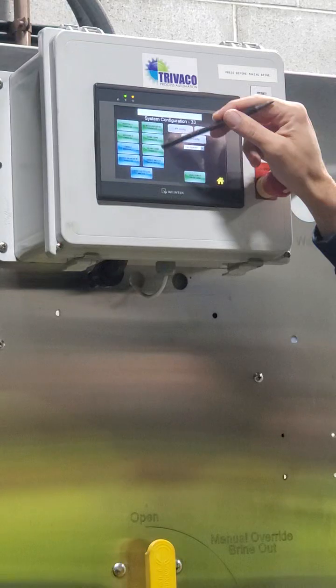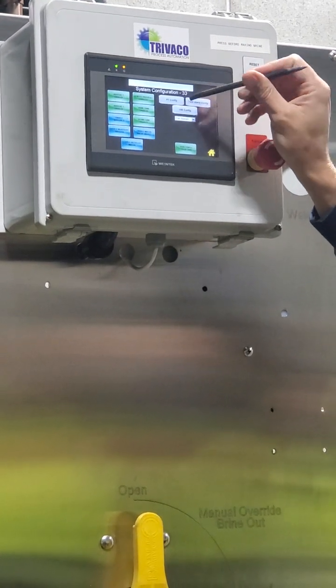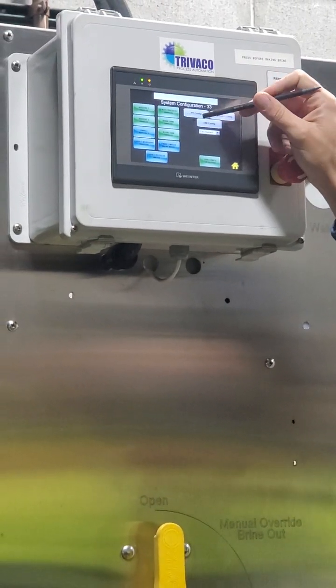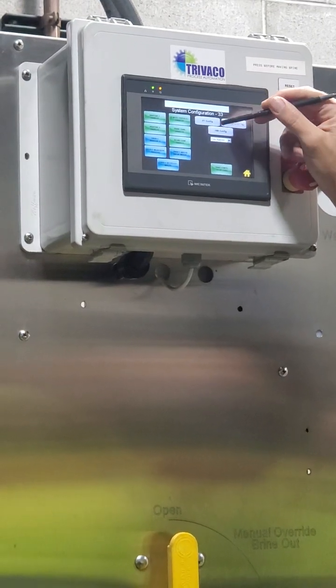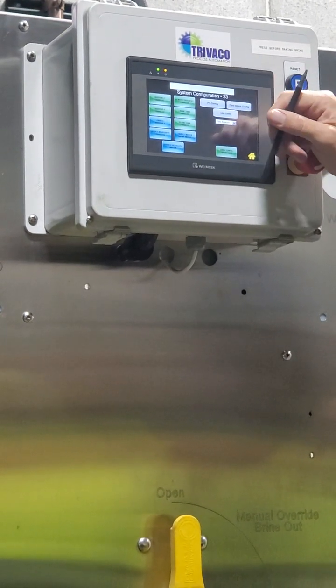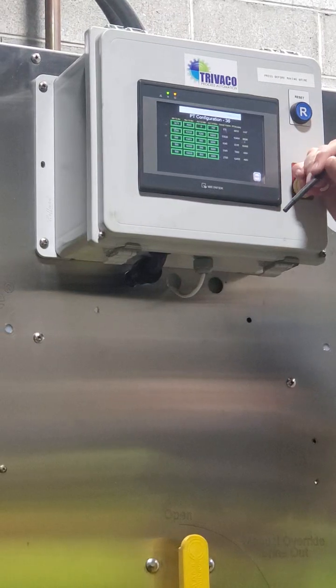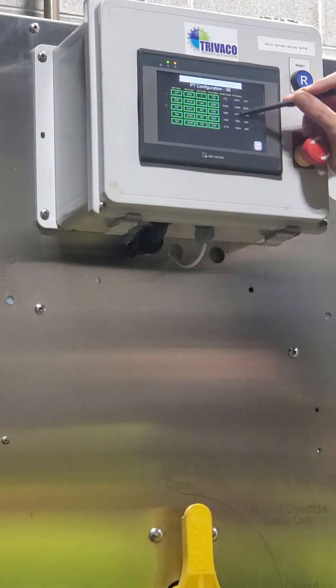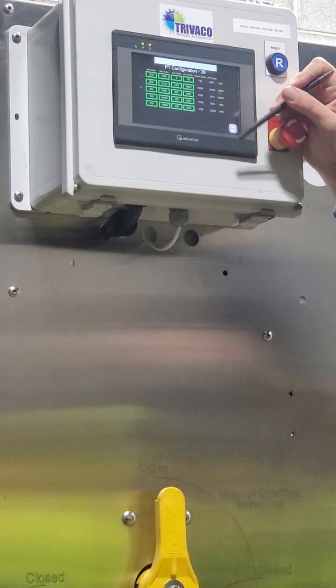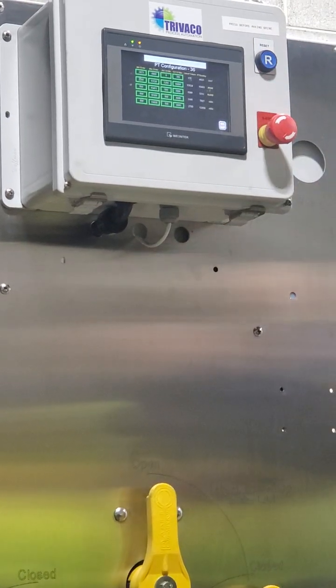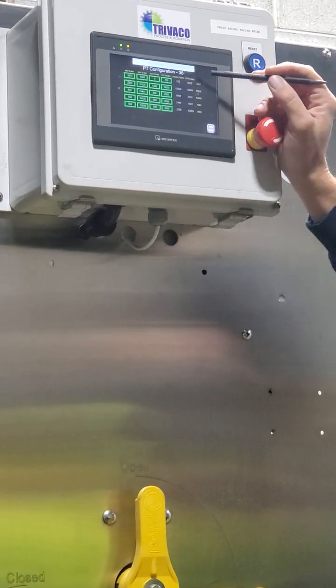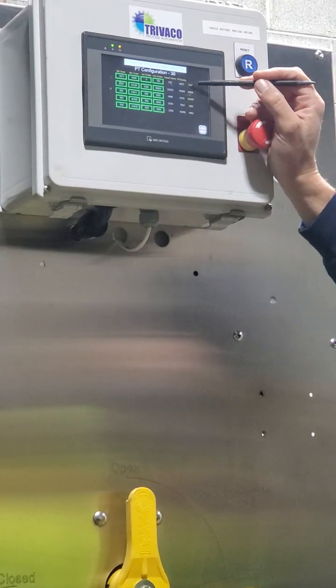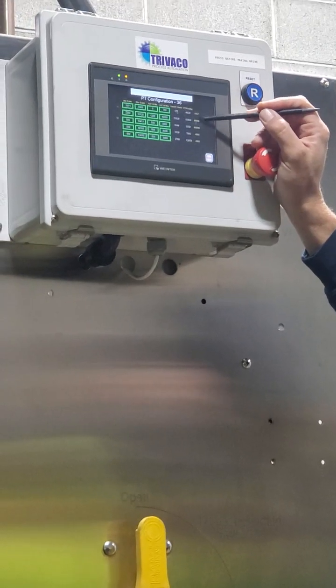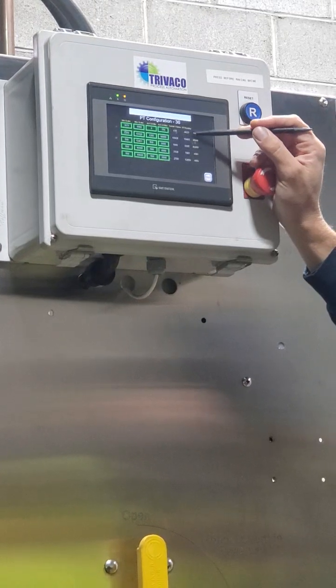You shouldn't have to touch or turn off any of those. If we go through all these great buttons, the key one here is the pressure transducer configuration page. That's PT config. PT means pressure transducer, and those are the little silver guys on top there. If you go in here, this is the actual reading right here on the right-hand side. That's the reading it's giving us back right now from every one of them. So the salt and the brine, if that PT goes bad, those are going to read 3200.